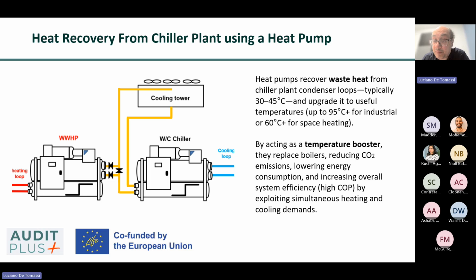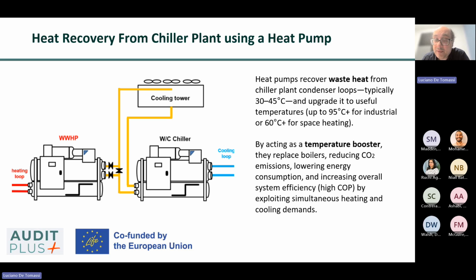Integrating a heat pump with a chiller plant transforms the system from a purely cooling-focused installation into a combined heating and cooling energy system by upgrading condenser waste heat from approximately 30 to 45 Celsius degrees to useful heating temperatures up to 60 degrees or even higher. It maximizes the energy recovery, improves the system efficiency, and enables significant reductions in boiler-related fuel use.